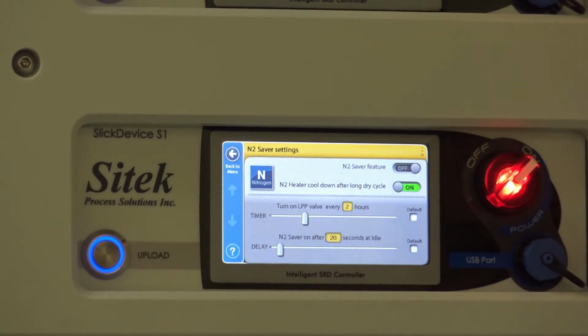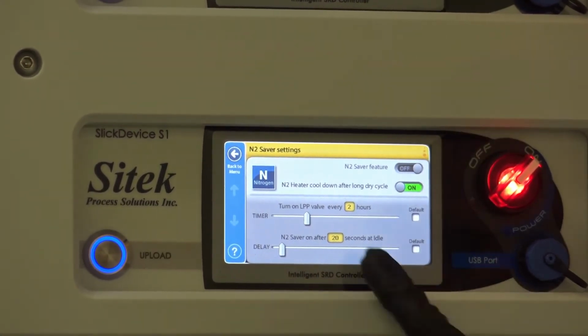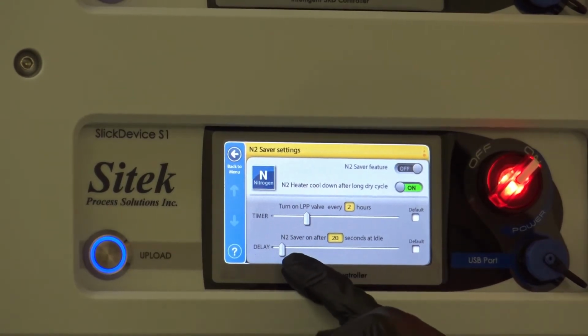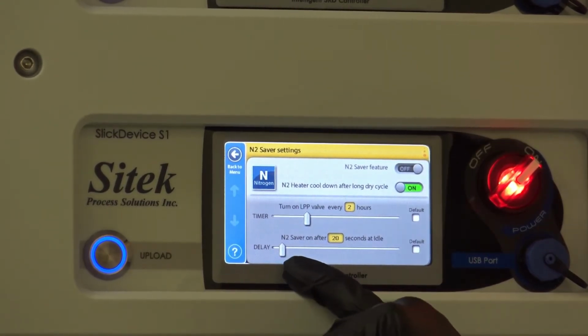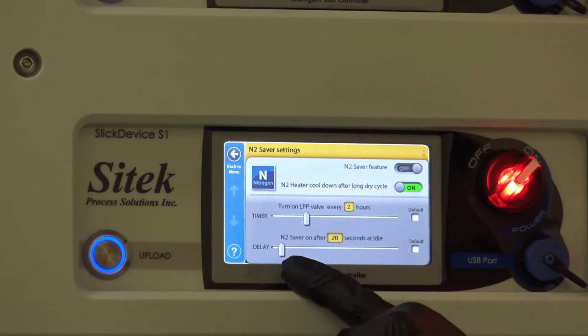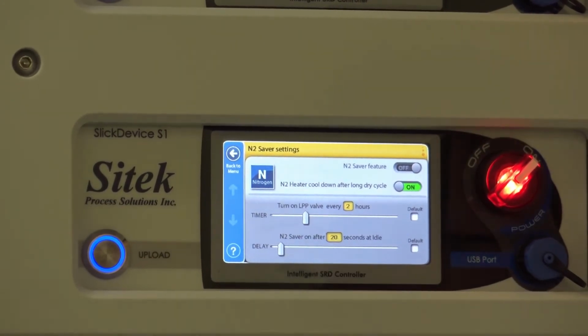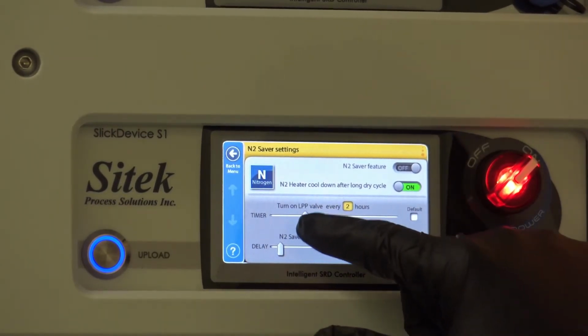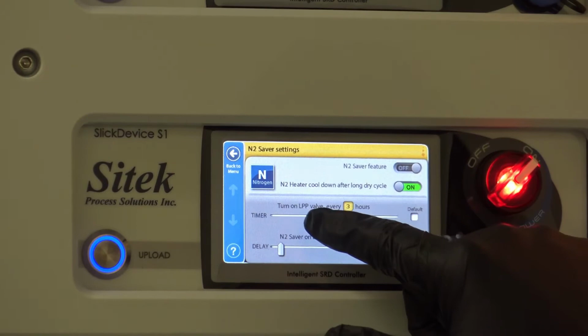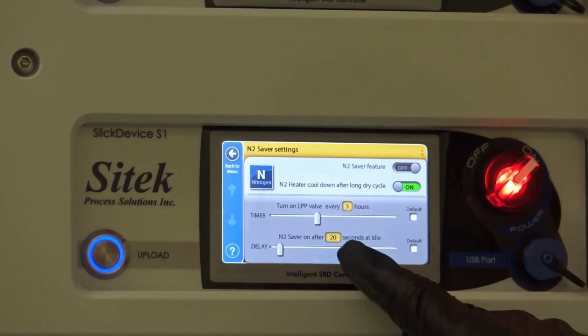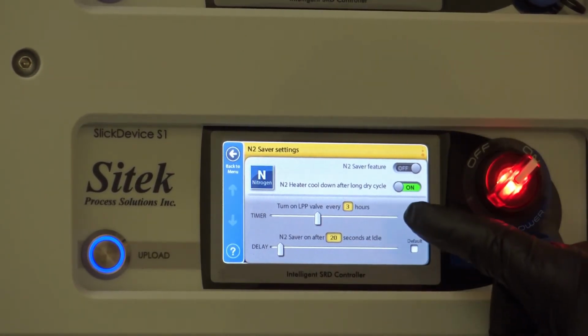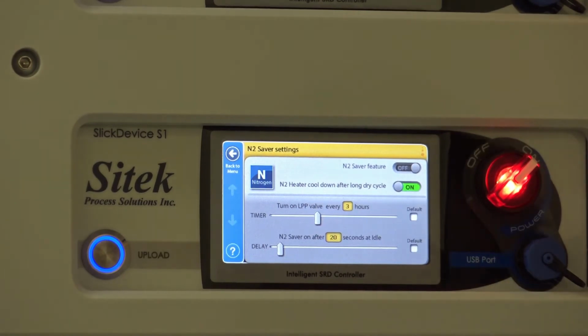What you can do in our system is at the end of the process, when the door's opened, after it closes, you can set the time. How long of a delay before we turn the LPP off? And then some customers have said, you know what, I want to have a purge every once in a while to keep my bowl a little pressurized and clean. You can program this. It says, okay, every 3 hours, I want you to come on and run that 20 seconds again. We also have what's called the N2 heater cool down.